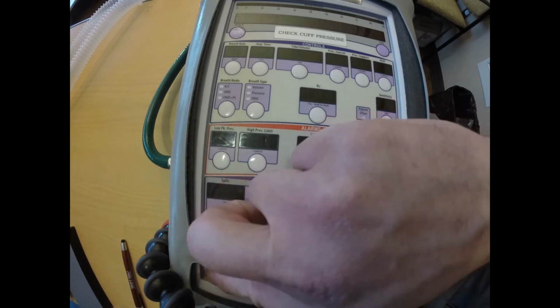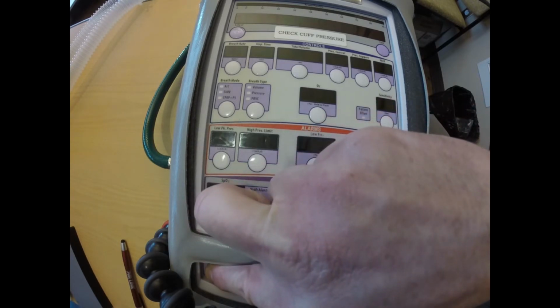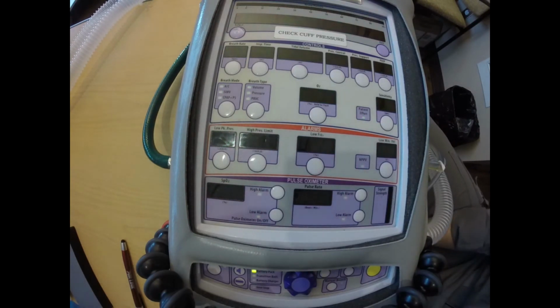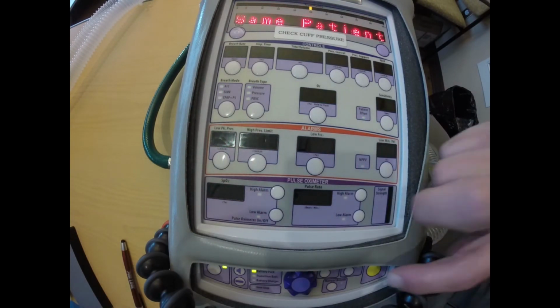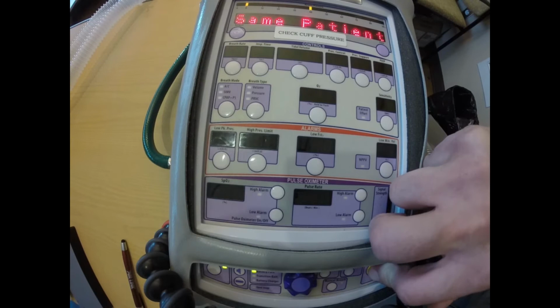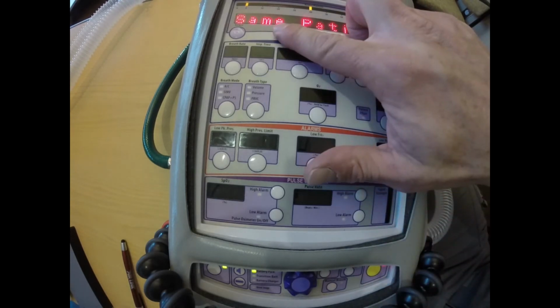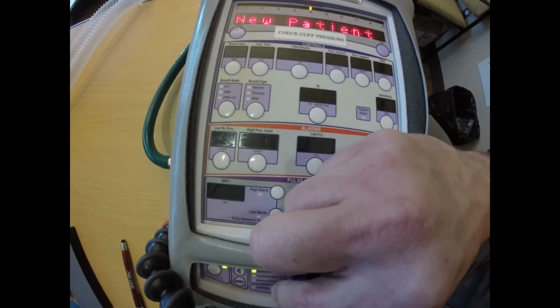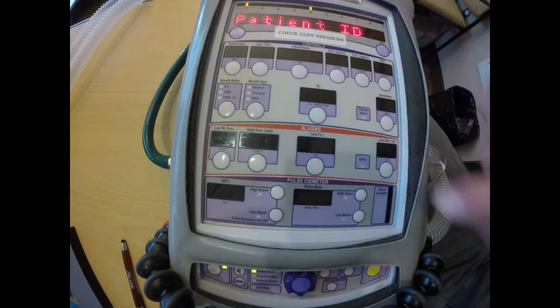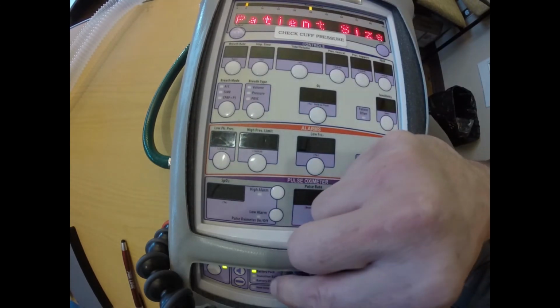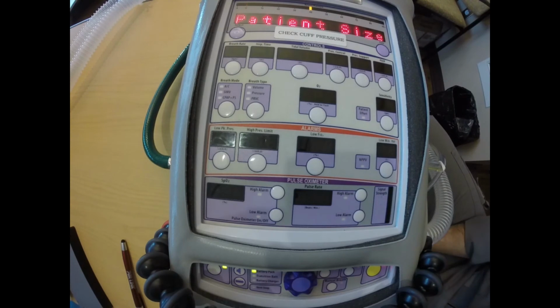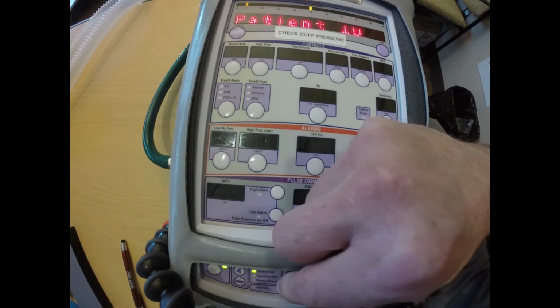So we're going to go ahead and turn our ventilator on like we always would. We're going to silence a couple of alarms like we always would. And we're going to choose a new patient using our toggle switch. So we choose new patient. We don't care about their ID. We do care about their size. Know that you could use BPAP or CPAP plus pressure support in a neonate, pediatric, or an adult patient. For the example, we're going to choose an adult patient.